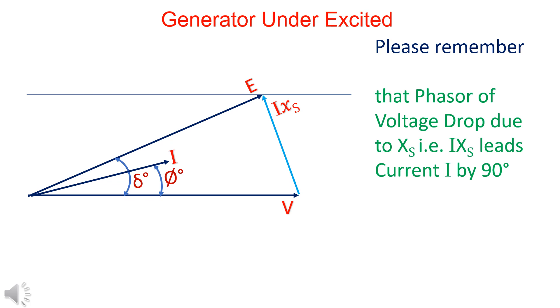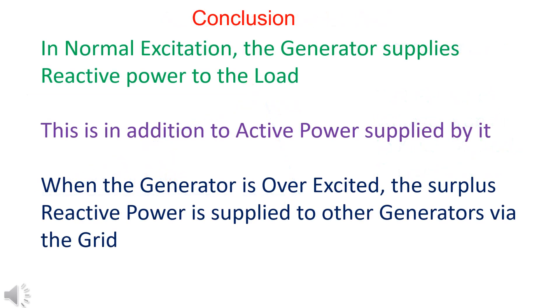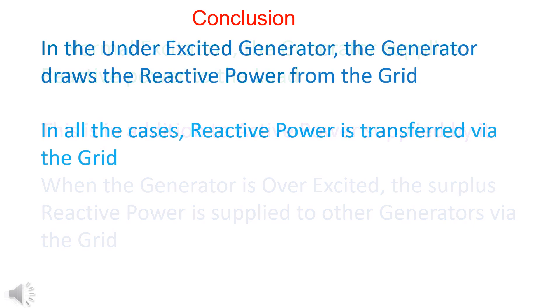Always remember that the phasor of IXs leads the current by 90 degrees. There is a misconception that only over-excited generators supply reactive power to the grid. Normally-excited generators also supply reactive power to the grid. The reactive power provided by the normally-excited generator caters to the requirement of the load. The excess reactive power of the over-excited generator is supplied to the under-excited generator connected to the grid.